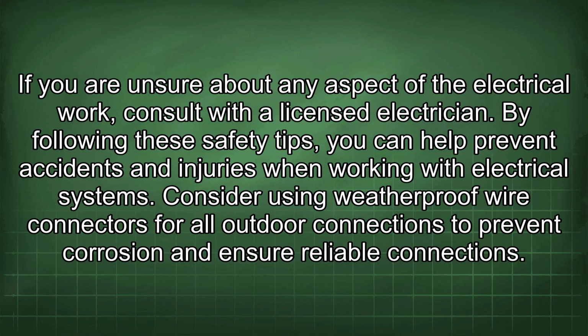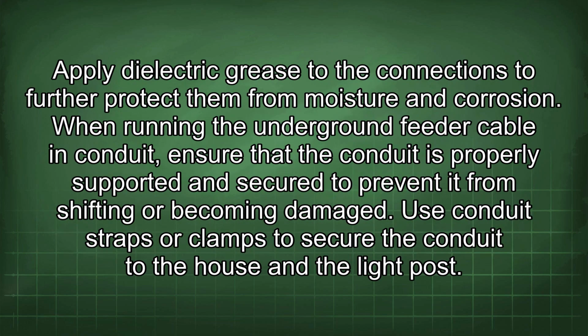Consider using weatherproof wire connectors for all outdoor connections to prevent corrosion and ensure reliable connections. Apply dielectric grease to the connections to further protect them from moisture and corrosion. When running the underground feeder cable in conduit, ensure that the conduit is properly supported and secured to prevent it from shifting or becoming damaged. Use conduit straps or clamps to secure the conduit to the house and the light post.